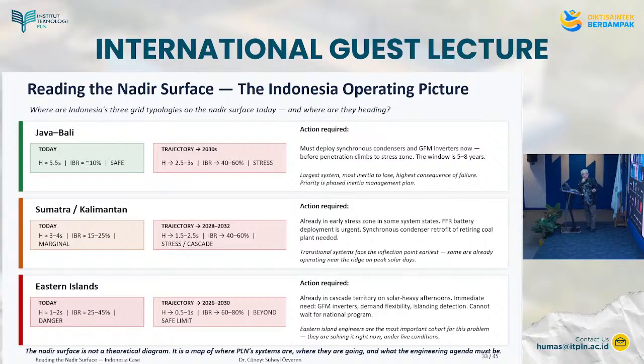So, okay, today is 5.5 seconds for Java Bali, 10% IBR renewable energy. The trajectory for 2030 is 40 to 60% renewable energy, and then the inertia constant will come down to between 2 and 3. So that Java Bali in 2030 will be in kind of a stress zone. Must deploy synchronous condensers and grid forming inverters now before penetration climbs to stress zone. And the window for doing that is 5 to 8 years. So within 5 to 8 years, those will have to be done.